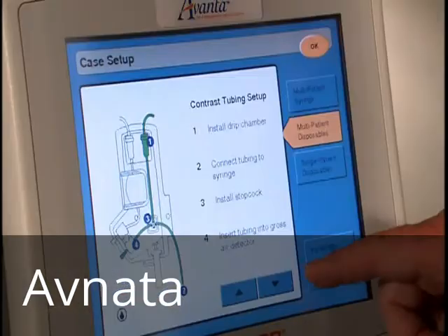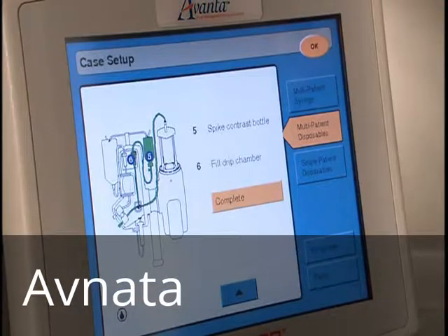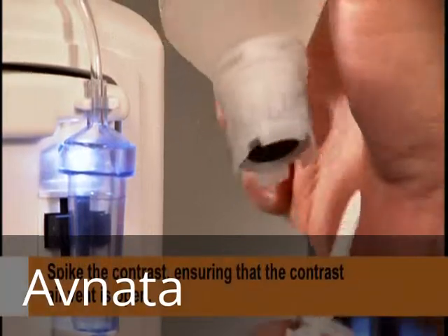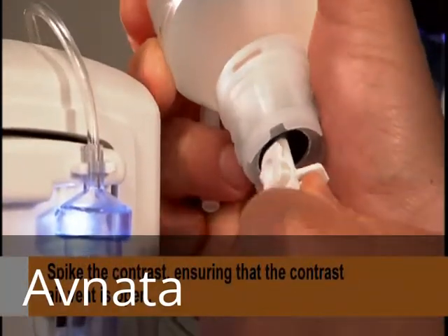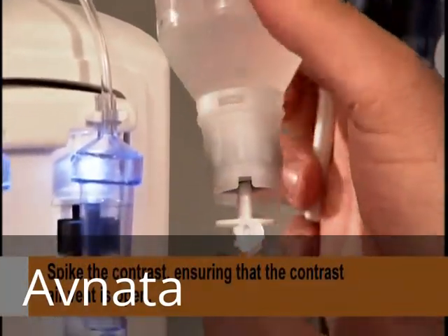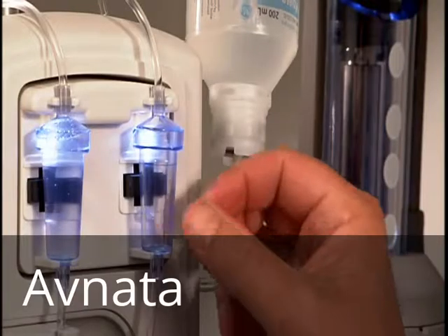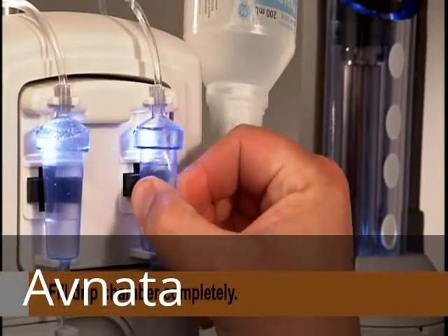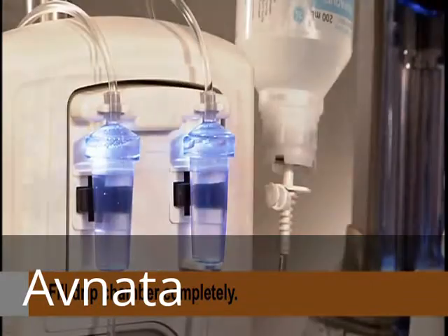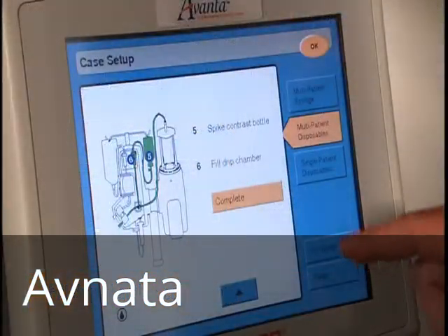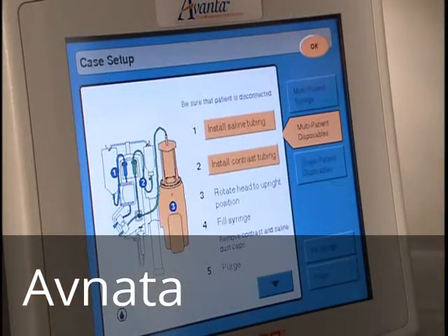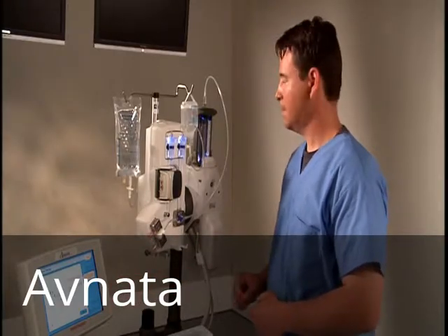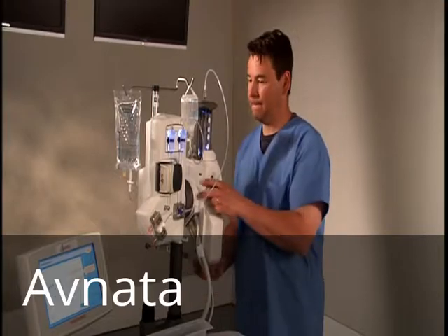Next, touch the down arrow to view the remaining steps. Step 5. Spike the contrast, ensuring that the contrast air vent is open. Step 6. Fill the contrast drip chamber completely. Then touch Complete. Next, complete Step 3 and confirm that the injector head is in the upright position.